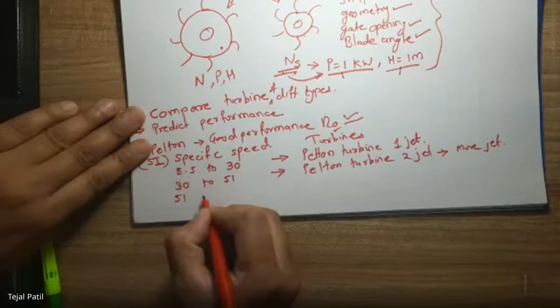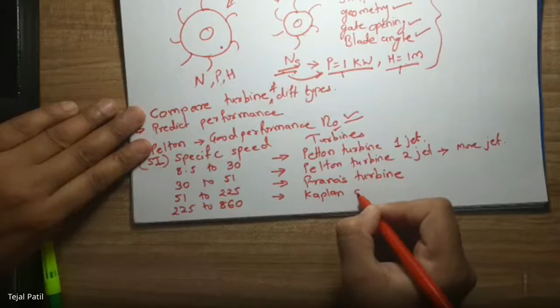And let's say it moves further from 30 to 51. Then you should select again the Pelton turbine, but the number of jets should be 2, or maybe more, depending on the availability of the nozzle which you are having. Then further, if the specific speed comes in between 51 to 225, then you should select the Francis turbine. And if it is 225 to 860, then either Kaplan or propeller.